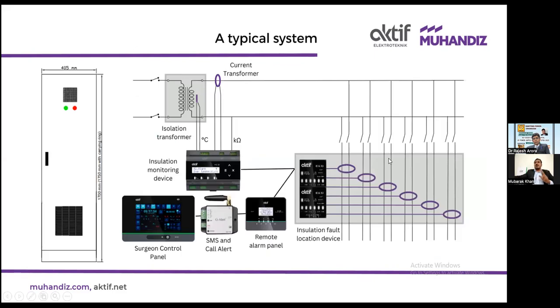Okay, so simplifying it more, a system after the isolation transformer will look something like this. There will be an isolation transformer, and then there will be an insulation monitoring device. The insulation monitoring device will take feedback, like input from the phase, to measure the resistance. It will take input from a current transformer in the outgoing of the isolation transformer to measure the current which it is feeding, and it will monitor the temperature of the transformer. If any of the parameters goes high, it will give an alarm, just to be sure that the transformer itself does not fail.